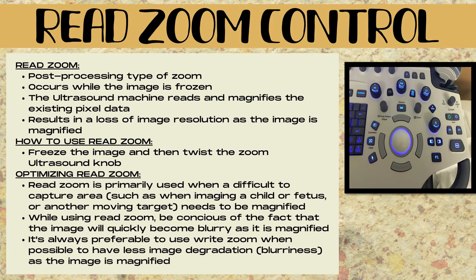Read zoom is a post-processing type of zoom, and this occurs while the image is frozen. The ultrasound machine reads and magnifies the existing pixel data, and this results in a loss of image resolution as the image is magnified.